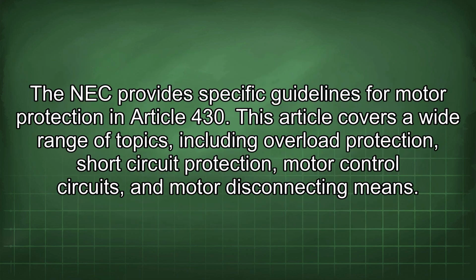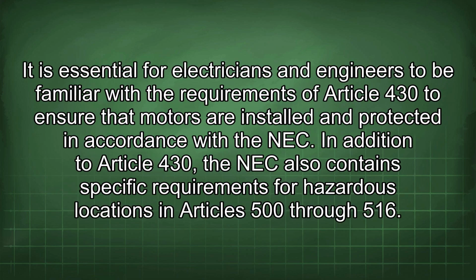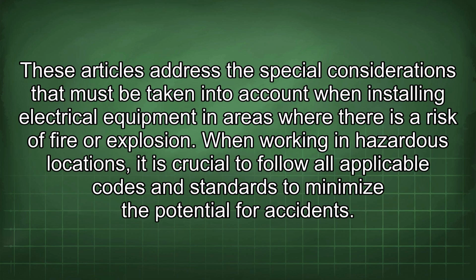The NEC provides specific guidelines for motor protection in Article 430. This article covers a wide range of topics, including overload protection, short-circuit protection, motor control circuits, and motor disconnecting means. It is essential for electricians and engineers to be familiar with the requirements of Article 430 to ensure that motors are installed and protected in accordance with the NEC. In addition to Article 430, the NEC also contains specific requirements for hazardous locations in Articles 500 through 516. These articles address the special considerations that must be taken into account when installing electrical equipment in areas where there is a risk of fire or explosion. When working in hazardous locations, it is crucial to follow all applicable codes and standards to minimize the potential for accidents.